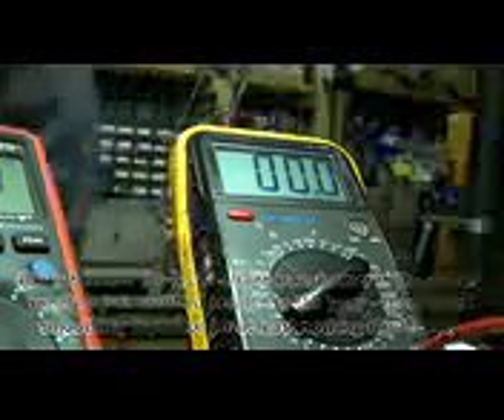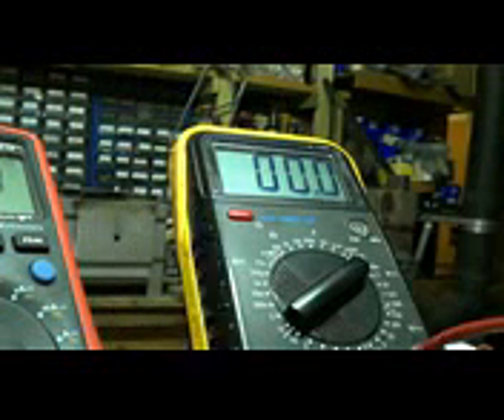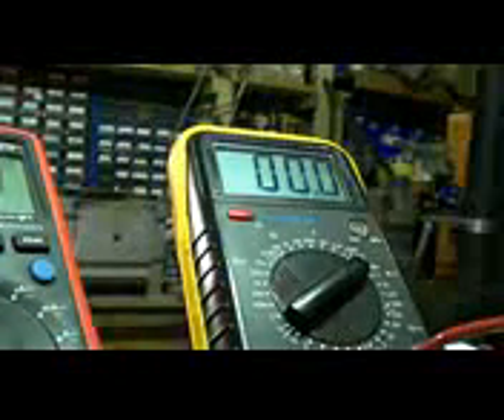So let's work out what that actually is. Remember it was 3.8 milliamps, and remember the divider is at 460,000 times division. So it's, what did I say, 22 millivolts times 460,000, which is about 10 kilovolts at 4 milliamps, which is about 40 watts going into the tube, which seems about right.